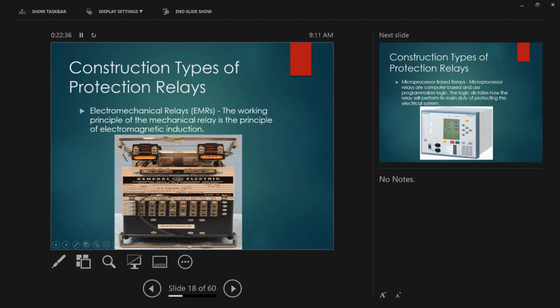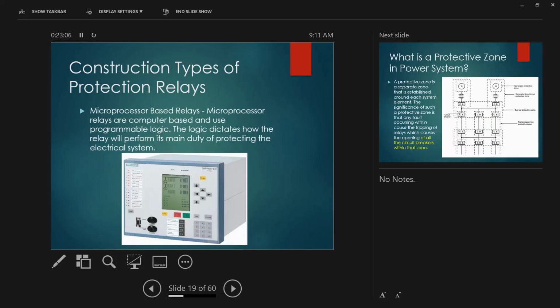In our time today, you just type what tap you want. But here you need to move this bolt. If you want a smaller tap, you move it to 3.2, 3.5. By the way, the common CTs that we used in those days were 500:5 and 200:5. All the secondary amps is 5 amps. In our time today, common is 1 amp because of the advancement of technology. Now, this is the new generation of relay.